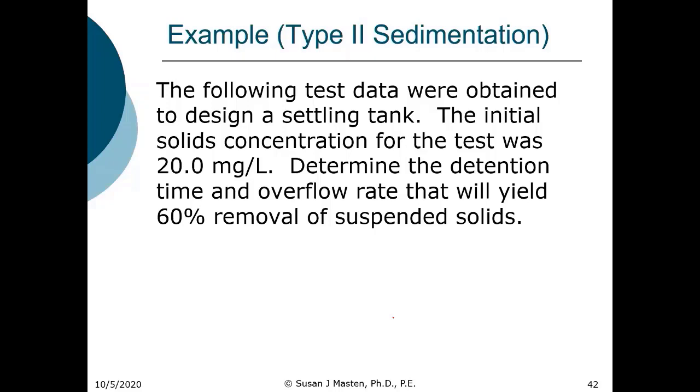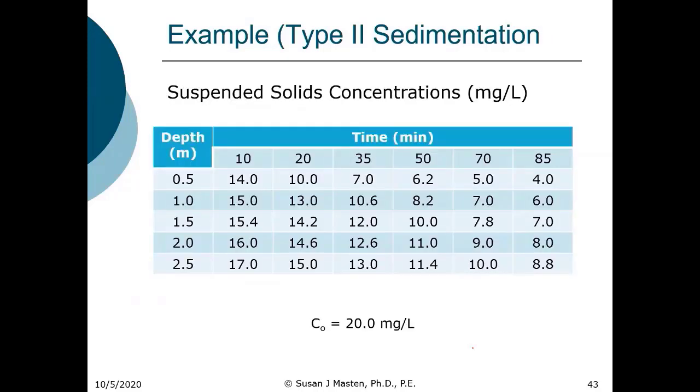In this example, the data from the settling test are provided along with the initial suspended solids concentration. You are asked to determine the detention time and overflow rate that will result in 60% removal of suspended solids. The data from the settling test are shown here.